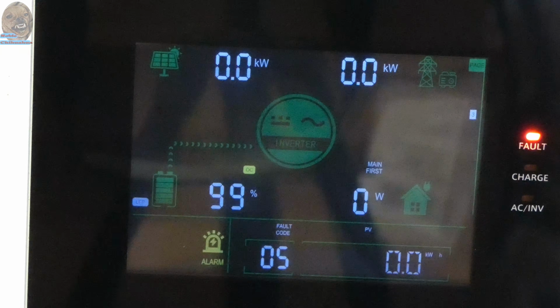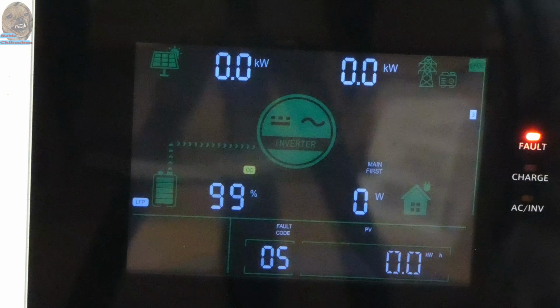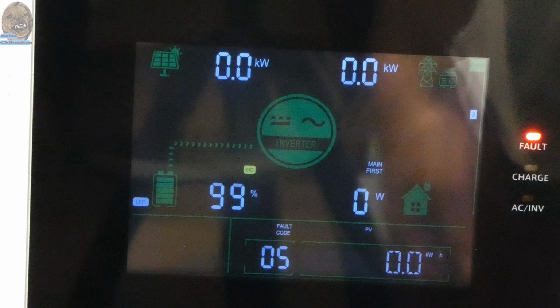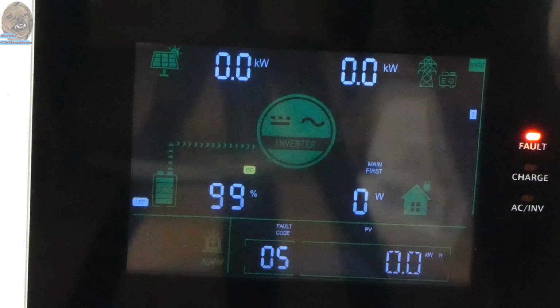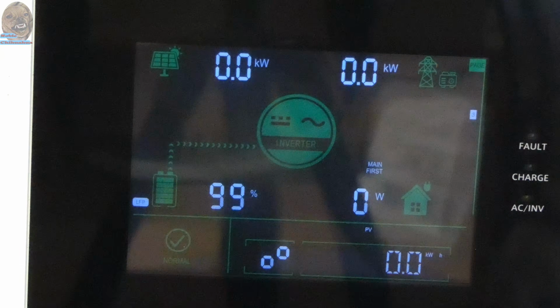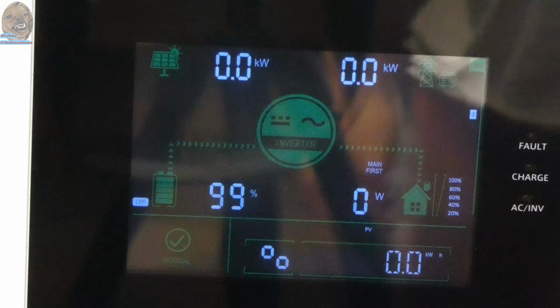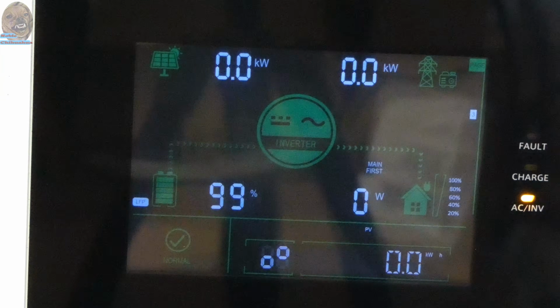As you can see, this unit was unable to run the compressor in its current configuration. Maybe when I set up a legitimate 20 amp circuit it will work, but who knows. I tried twice, but the system shut itself off each time. It recovered on its own, which is good.